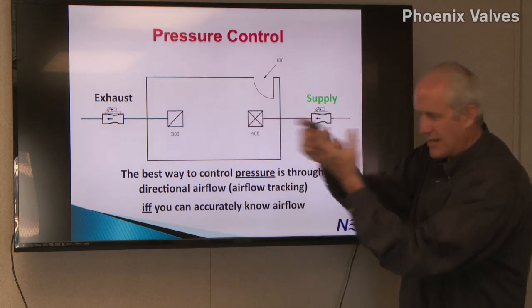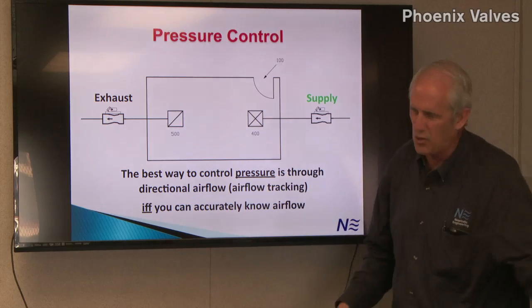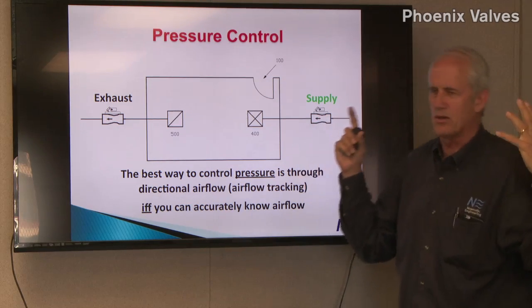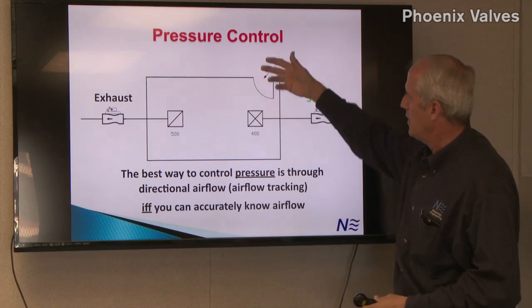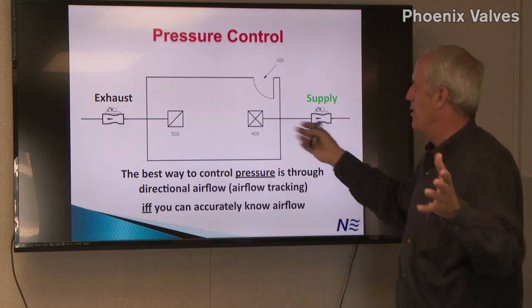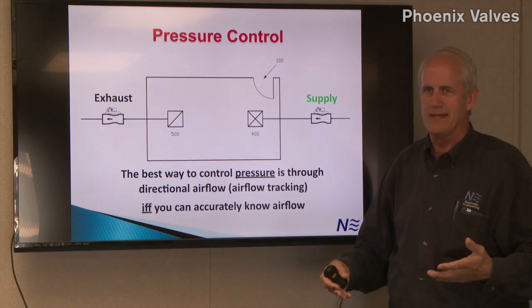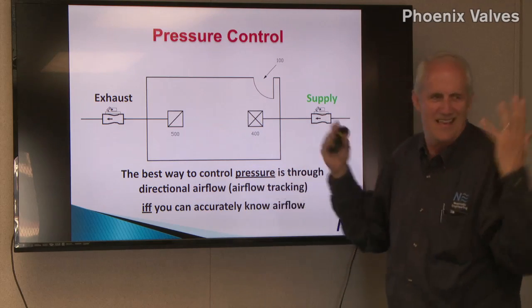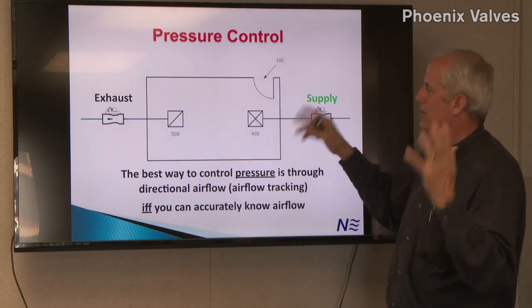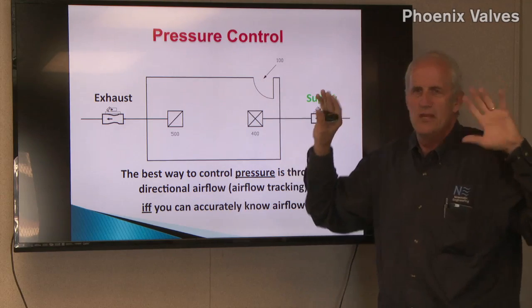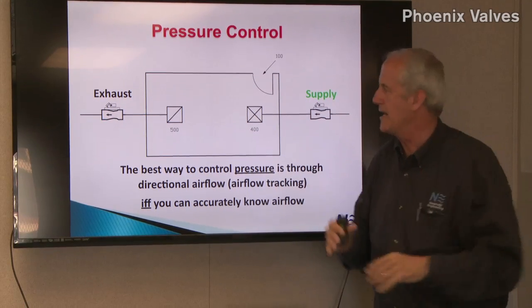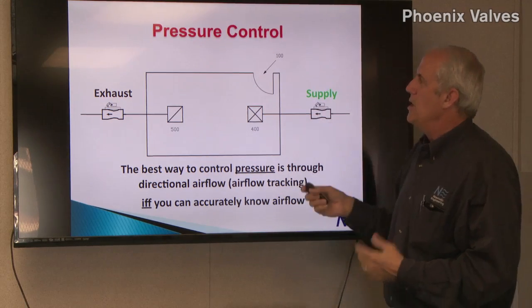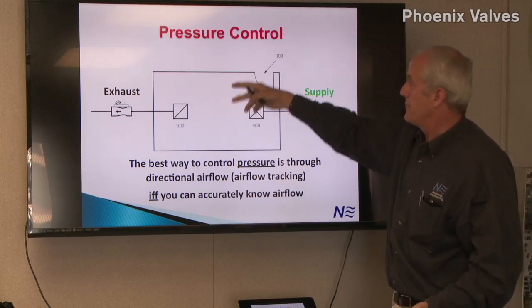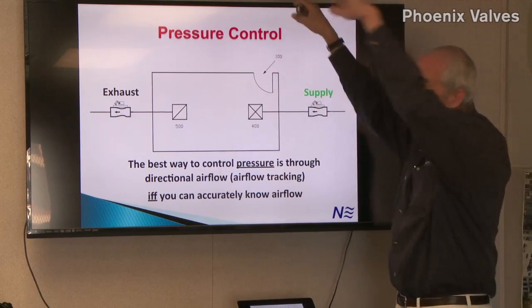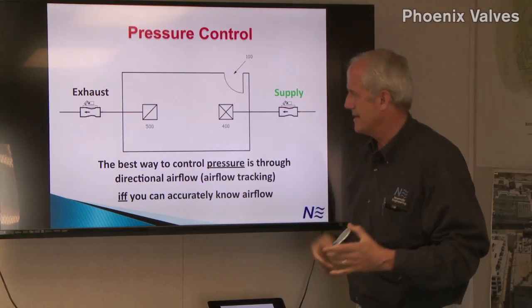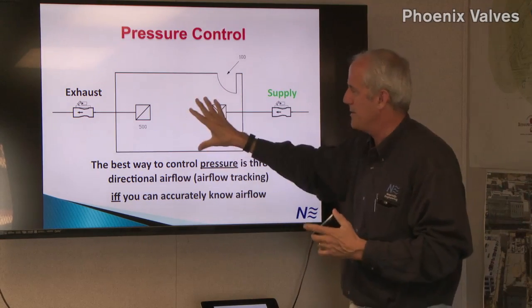Some people try to measure the pressure of the room, but you really run into problems because when you open the door, the system doesn't know what's going on. If you have a 20 square foot opening here and you pop that open, the relative pressure between these two spaces will literally be 0.00000. It's beneath a measurable value when you open the door. What will happen when you close the door, you will achieve some pressure differential. Vivariums are very tight spaces. You've got hard lids and gasketed access doors, and so it's going to be a tight space.